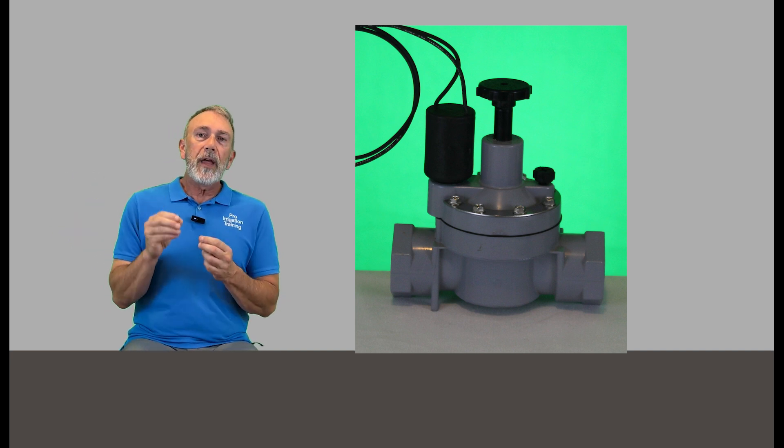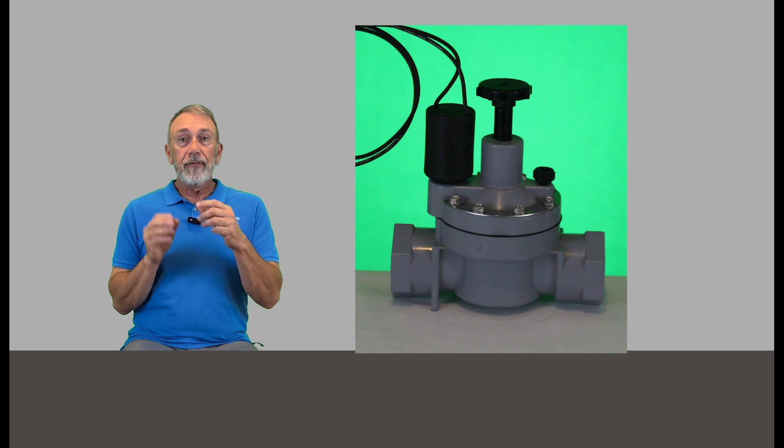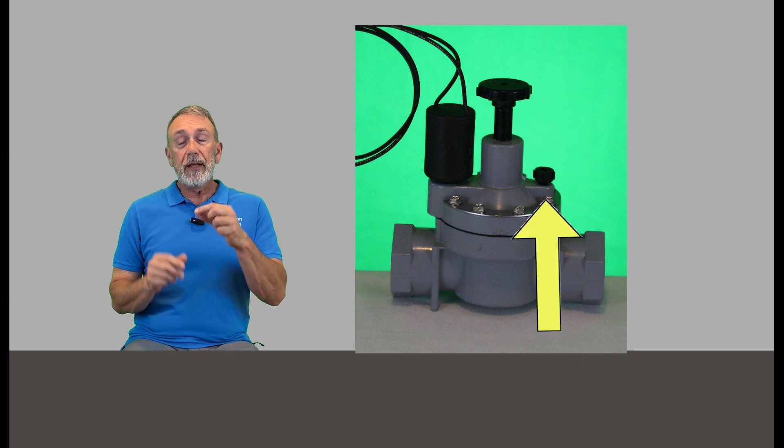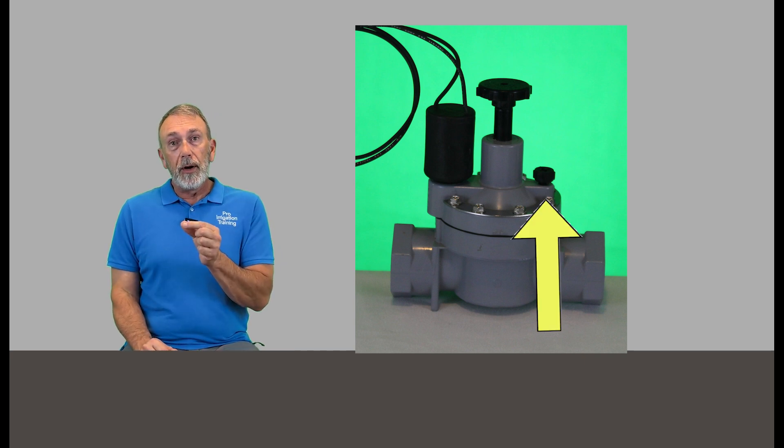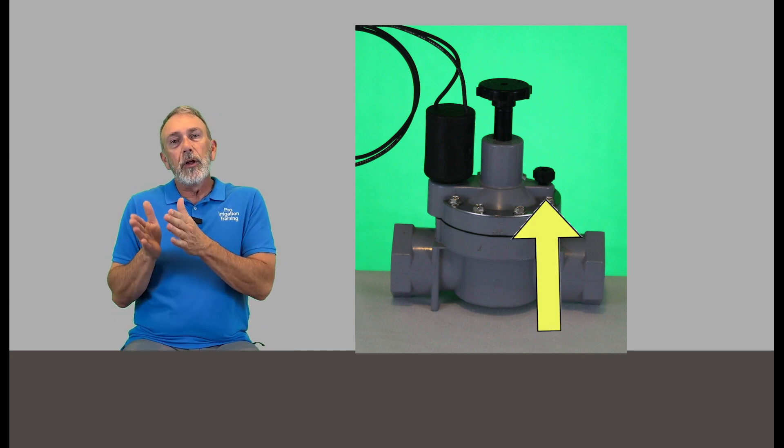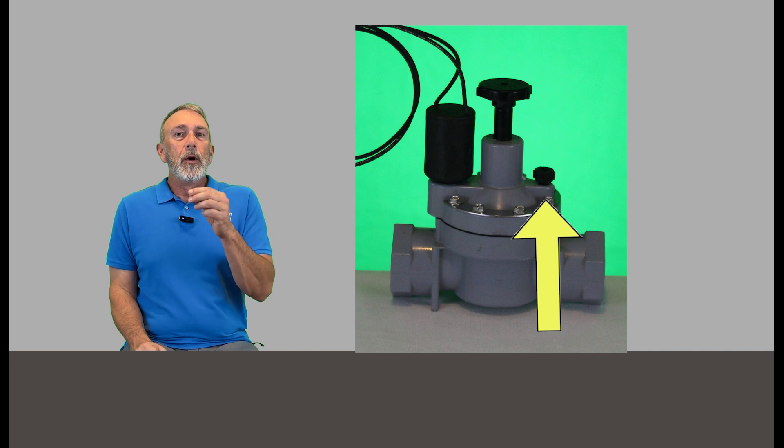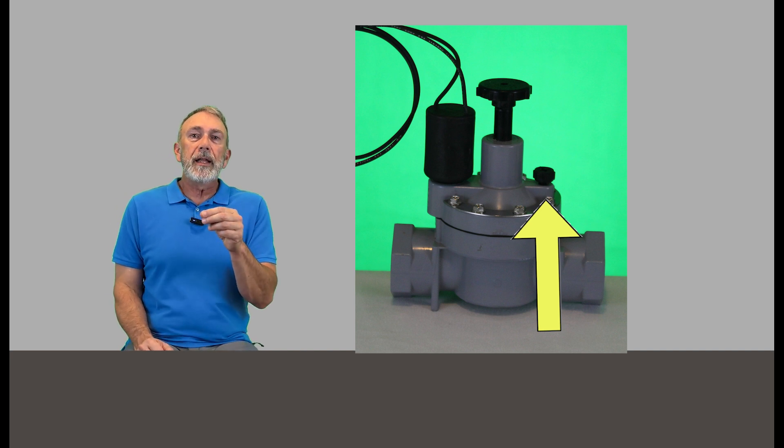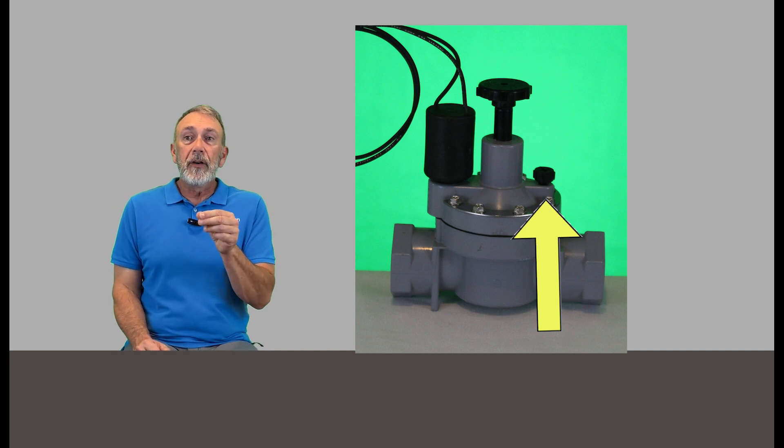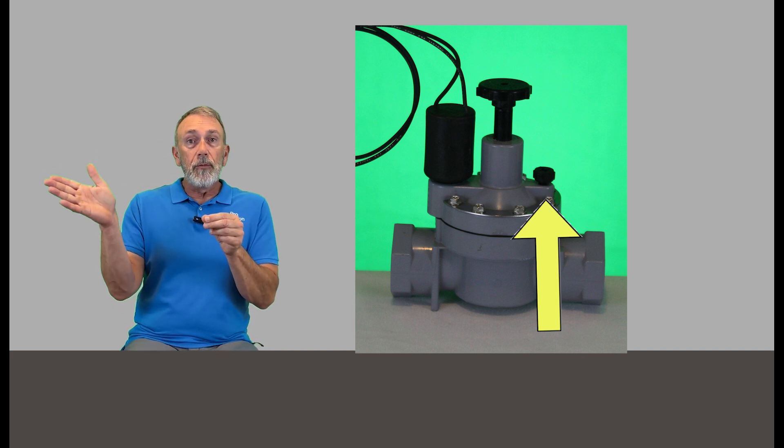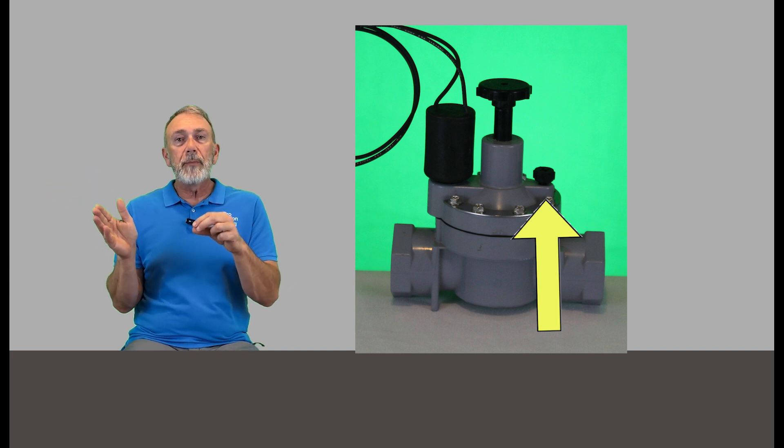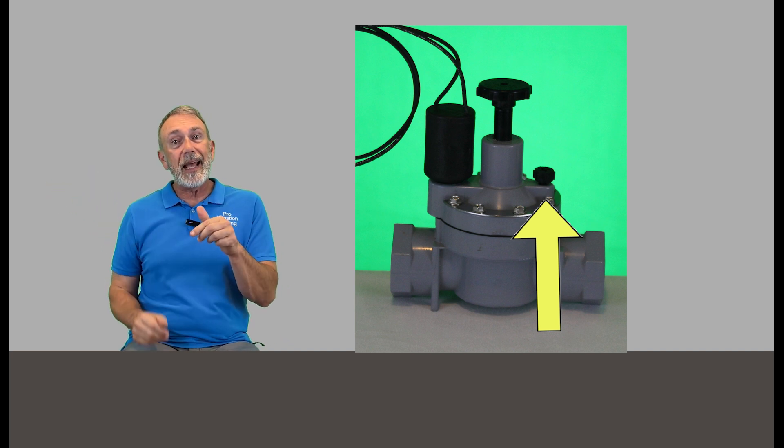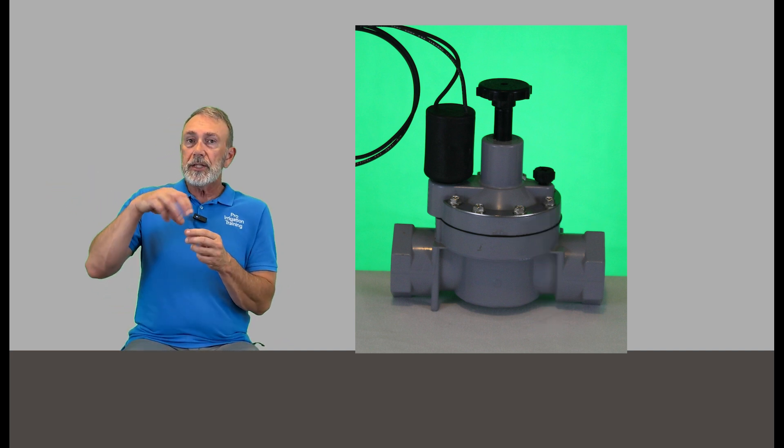While we're there at the master valve, we want to check if that doesn't do it, if there's a bleed screw on it, and not every valve has a flow control. We want to open up the bleed screw if not and see if that affects the zone that's running. And if not, we'll close it back. And if it doesn't have a bleed screw, let's open up the solenoid.